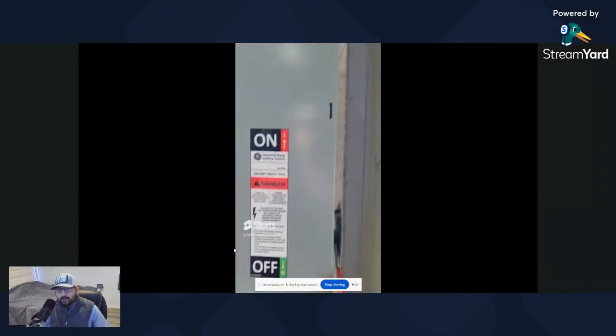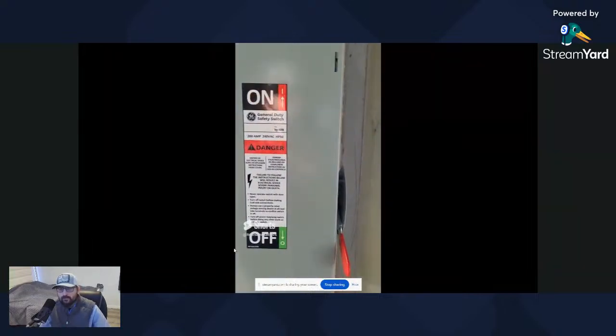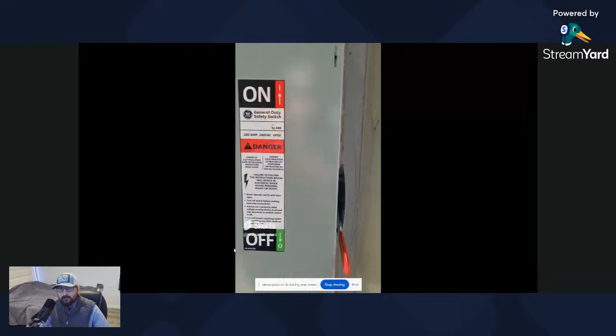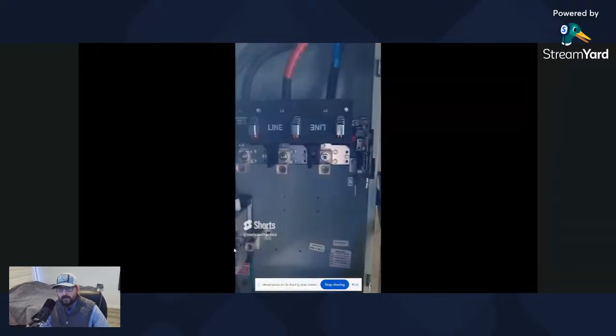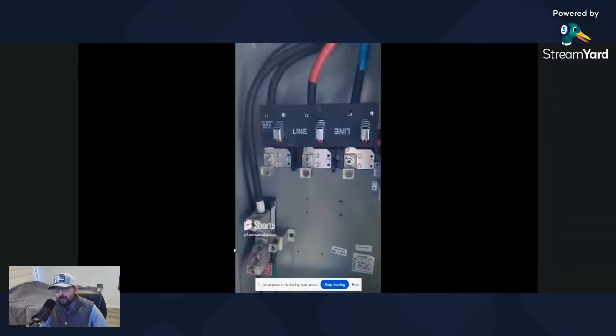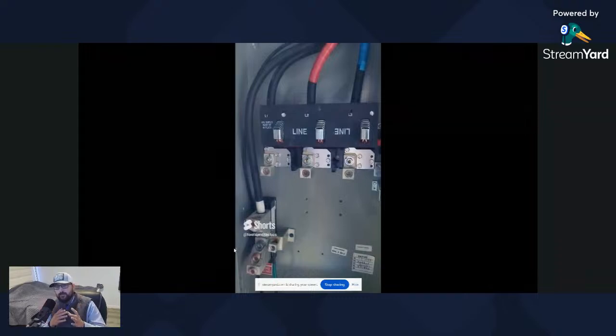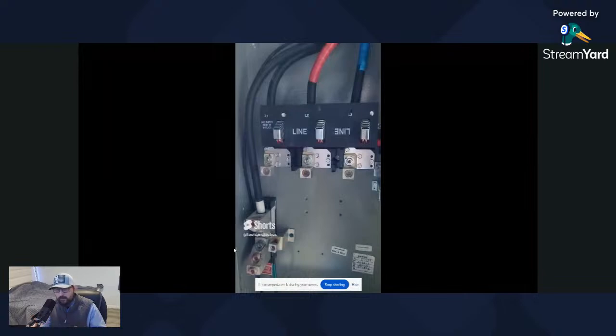There's a general duty safety switch right there. And that's exactly what that is. All it does is disconnect the power. There's no spots for fuses. There's no overcurrent protection. There's so much wrong with this because straight off of the transformer, it's like a service. They call them secondary conductors. And there's a lot of rules that have to go with secondary conductors.